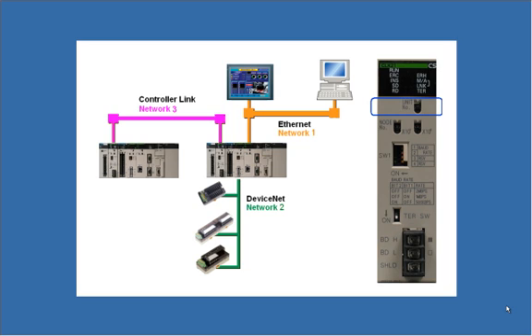In the picture that you see, there are two PLCs and three networks. Each of the two PLCs would have its own unique routing table that must be created and downloaded separately. There is not a generic routing table that gets downloaded to all the PLCs on the network. I will focus on creating the routing table for the PLC on the right for this example.